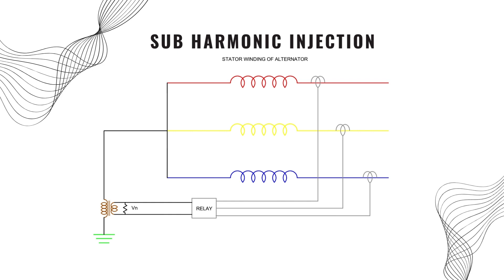Let's understand the working principle of this method. Subharmonic frequency means the frequency is less than the fundamental frequency. Here, 20 hertz frequency is injected through a bandpass filter across the secondary terminal of the NGT and a CT is connected to measure the current.